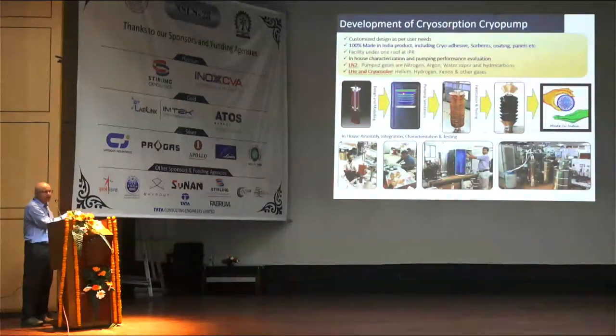If you use liquid nitrogen, which is what we've been using there, the pumped gases can be nitrogen, argon, water vapor, and hydrocarbons. So these are the applications that can be handled. If you start using liquid helium with a cryocooler, you can pump helium, hydrogen, xenon, and other gases. So this just shows you the various stages through which this thing goes through.